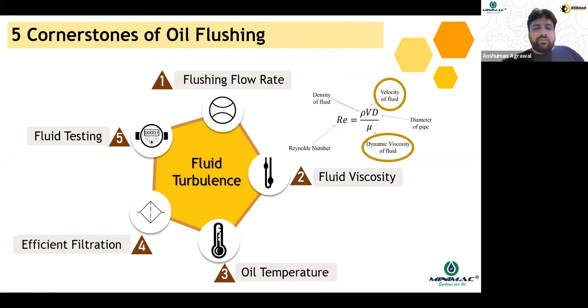The third one is oil temperature, because temperature would actually lead to changes in your oil viscosity, and it would also lead to certain efficient flushing requirements — those are called thermal shocks. We'll see all of this in much more depth in the subsequent slides. The fourth cornerstone is efficient filtration, because flushing is all about trapping contamination, and that's why you need efficient filtration as well. And the fifth cornerstone is testing — in order to conclude your flushing, you need a good measuring device for testing. So these are the five cornerstones of flushing.